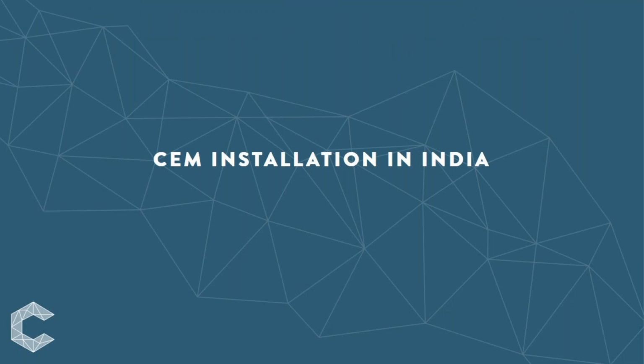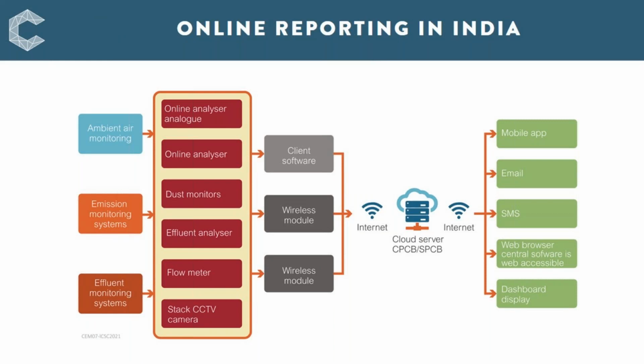So let's look at what is happening in India. As I mentioned earlier, the Indian government requires that CEM systems be installed at all relevant emission sources, including coal-fired power plants, on every single unit. The authorities also require that the data from these systems be delivered directly to the reporting agency in real time and in a tamper-proof manner. This means that CEM systems must be connected to the data handling system, which then feeds the data via the internet to the servers. These servers are monitored and controlled directly by the central and state pollution control boards, a system that's relatively advanced and quite unique to India in some ways in the level of security through the whole system.